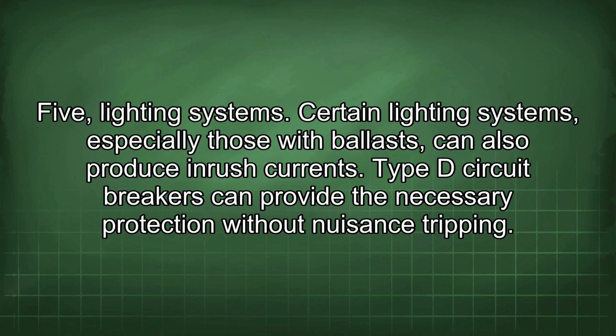5. Lighting systems. Certain lighting systems, especially those with ballast, can also produce inrush currents. Type D circuit breakers can provide the necessary protection without nuisance tripping.